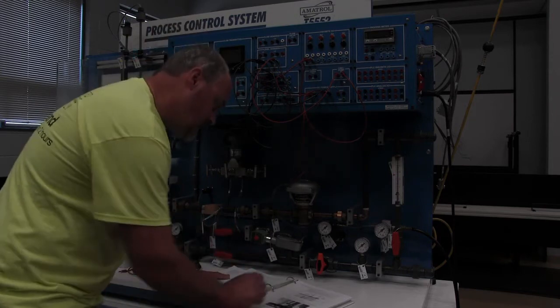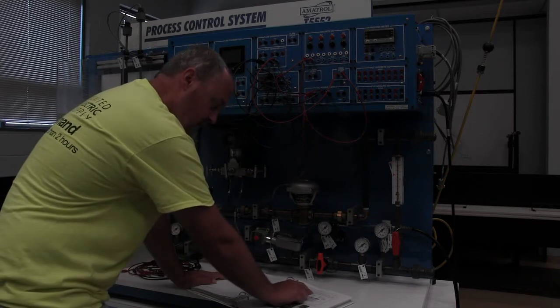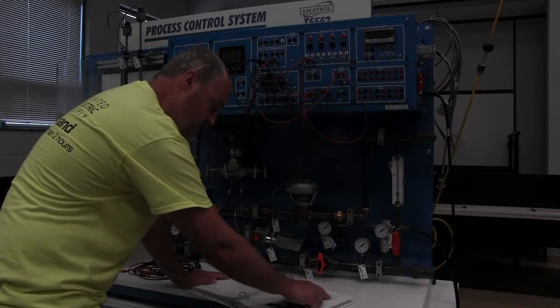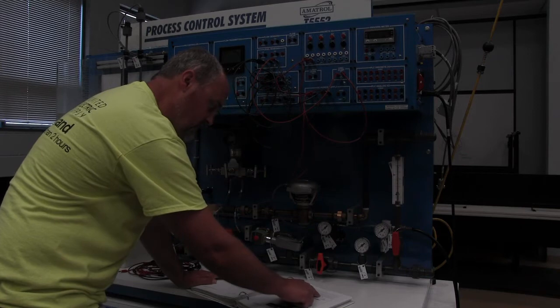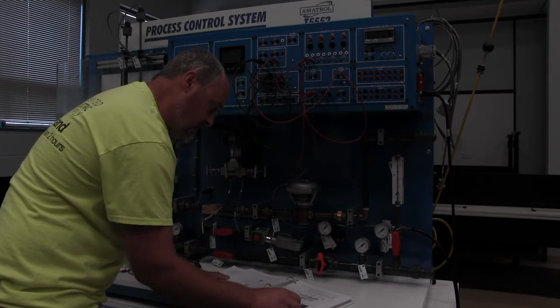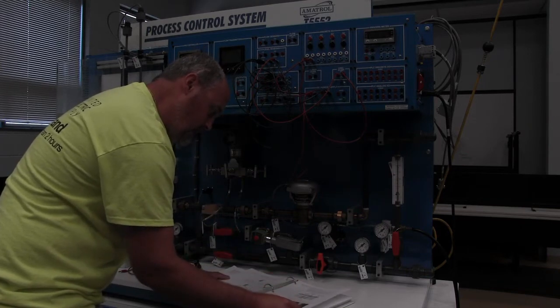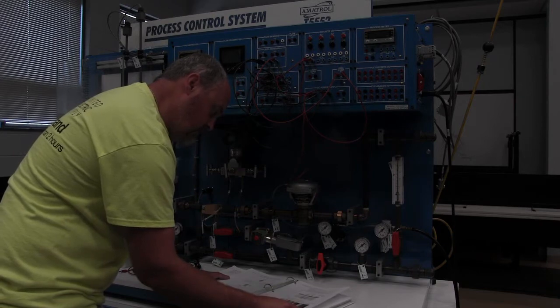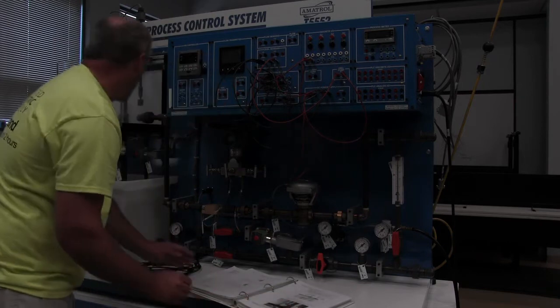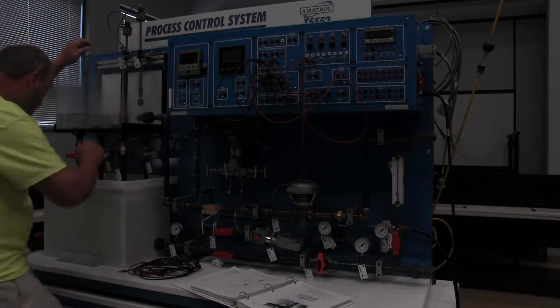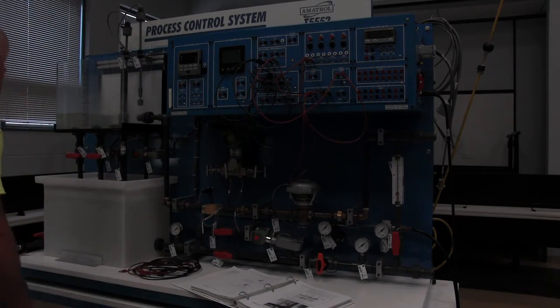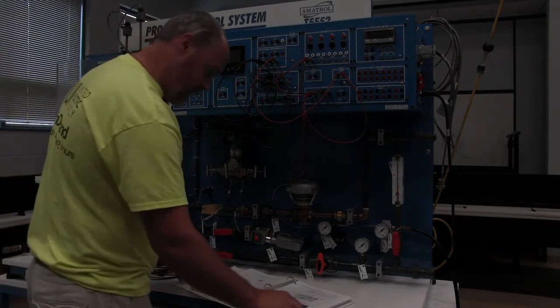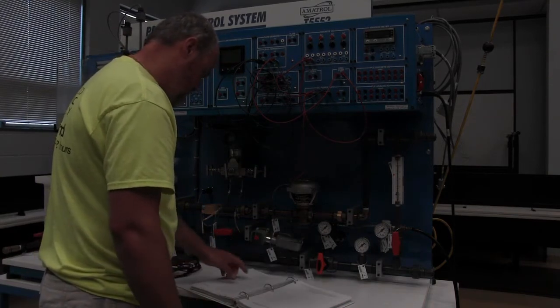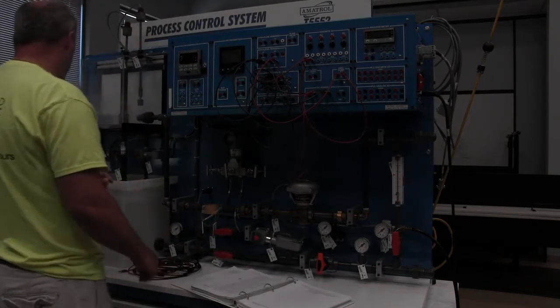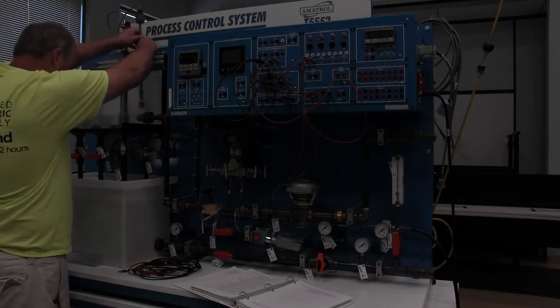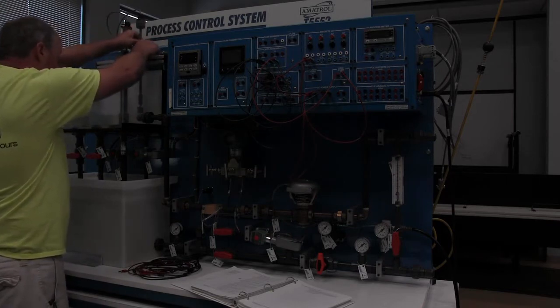So now it says loosen LSH 200A and adjust the screw by turning it counterclockwise to move it up or down the shaft, so the bottom of the switch is even with the 1-inch mark. So we're going to take A, and the bottom of the switch is pretty close to the 1-inch mark now, so we're going to leave that there. We're going to take B and have it close to the 2-inch mark, so we're going to want to lower this one a little bit. All right.